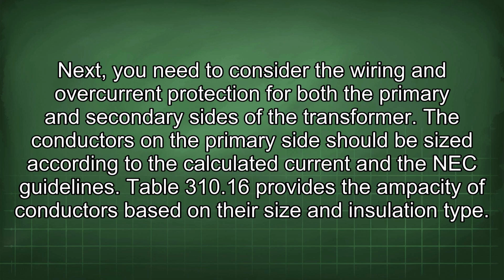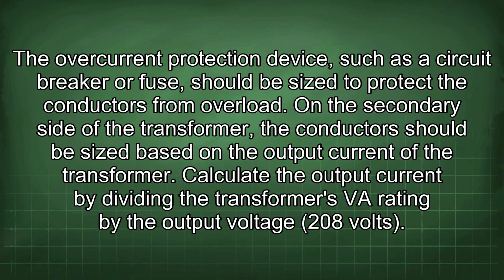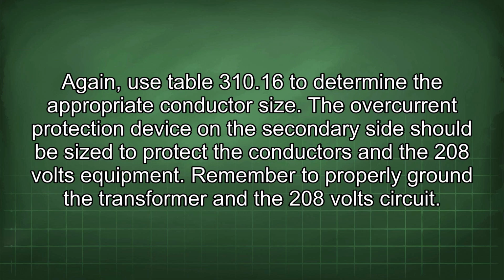Table 310.16 provides the ampacity of conductors based on their size and insulation type. The overcurrent protection device, such as a circuit breaker or fuse, should be sized to protect the conductors from overload. On the secondary side of the transformer, the conductors should be sized based on the output current of the transformer. Calculate the output current by dividing the transformer's VA rating by the output voltage, 208 volts. Again, use Table 310.16 to determine the appropriate conductor size.